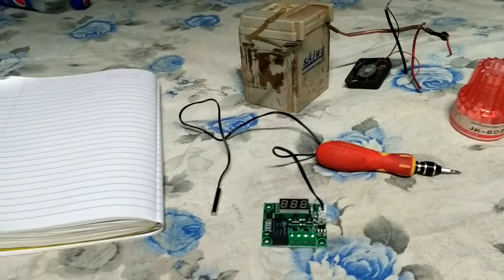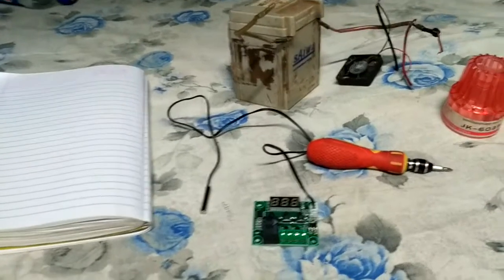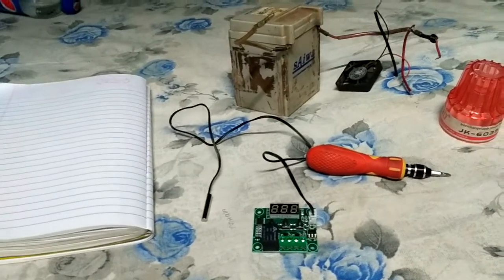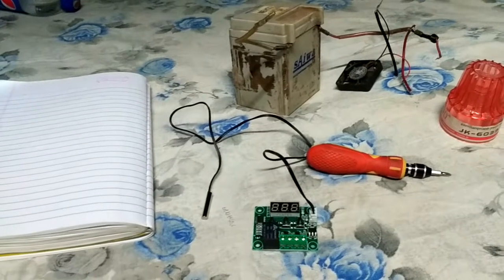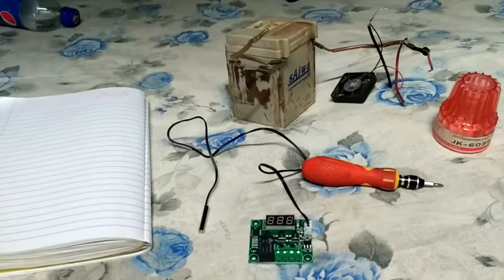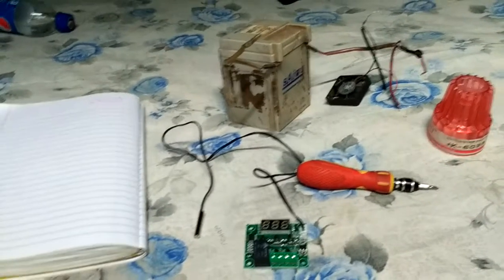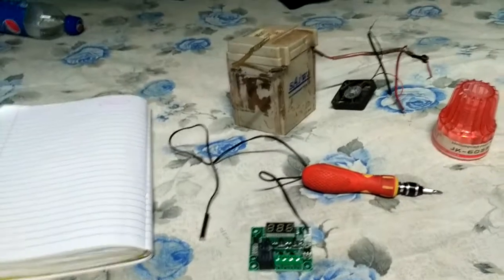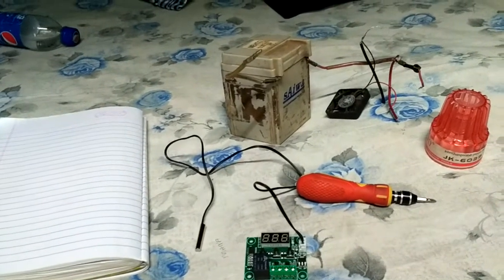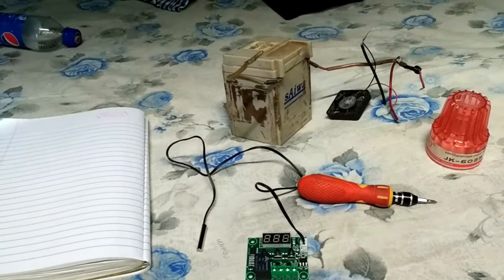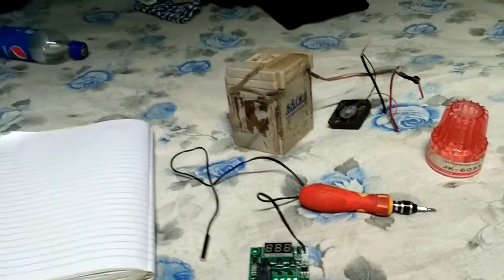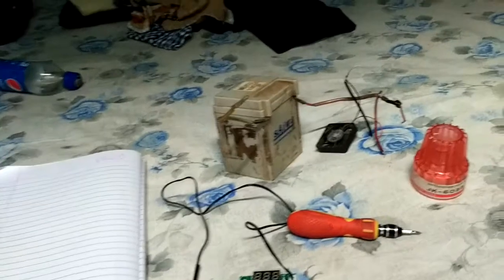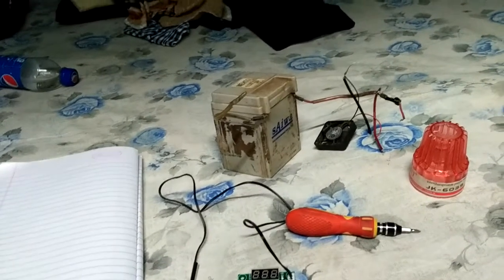We don't want more than that temperature - 10 degrees is sufficient. So your fridge will automatically switch off at 10 degrees Celsius and automatically turn on when the temperature rises 2 degrees, meaning 12 degrees Celsius. The temperature maintains a difference of 2 degrees Celsius. It will automatically turn off at 10 and on at 12.